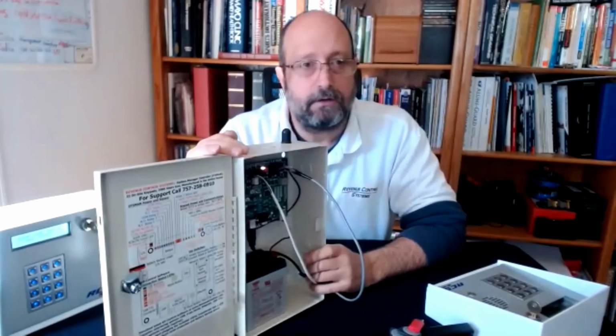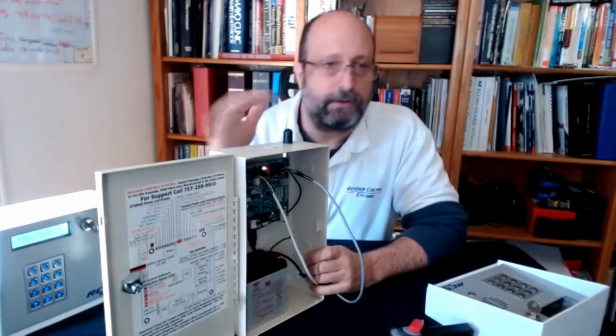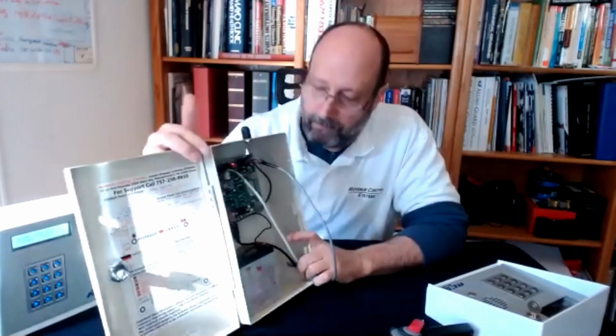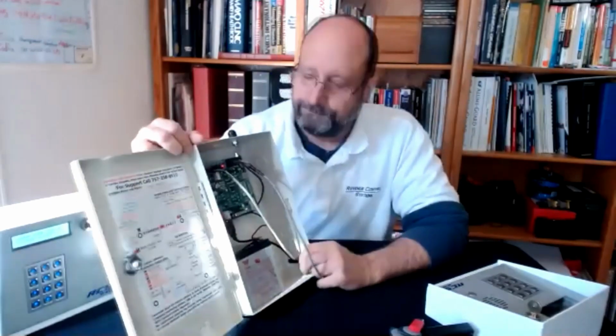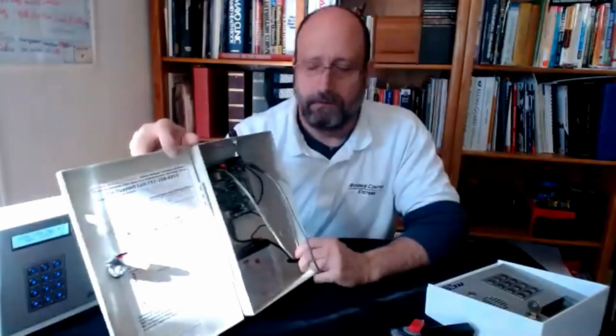But like I said earlier, RS-485 is very robust. It'll work on virtually any cable as long as it's not damaged in some way. And we do have literature that shows the specification on the wire. But you should always use shielded cable for these outdoor installs.